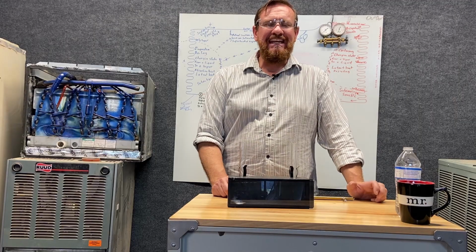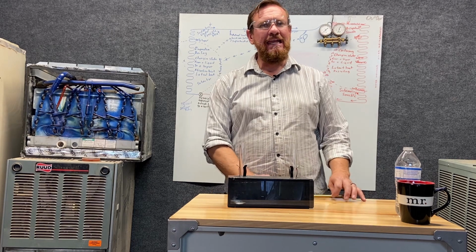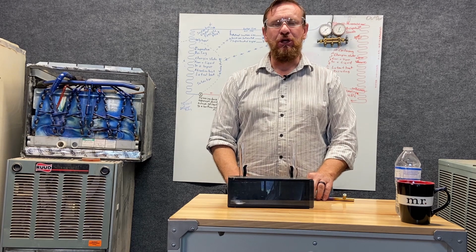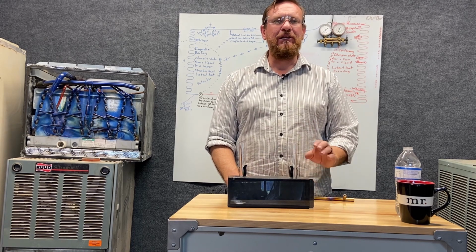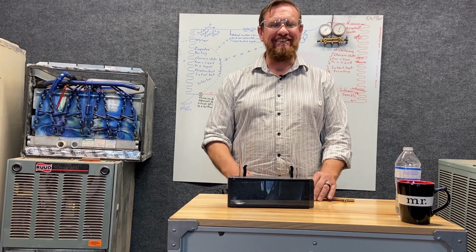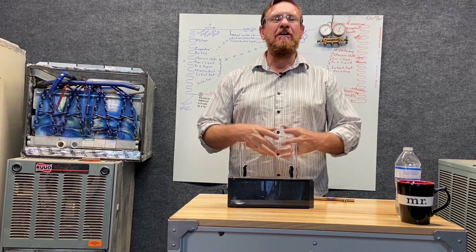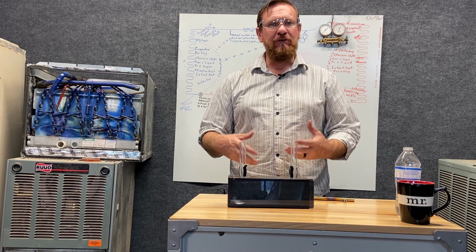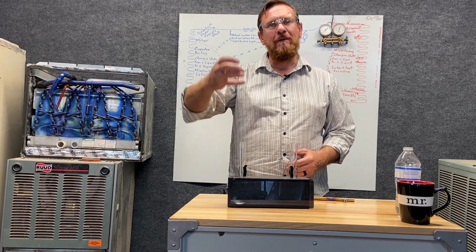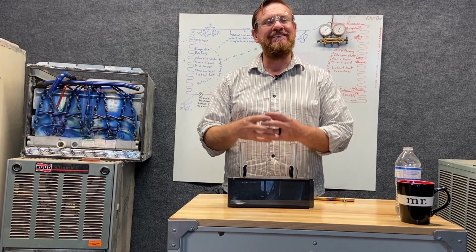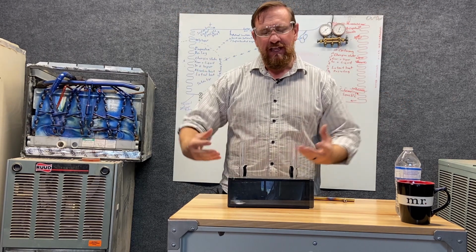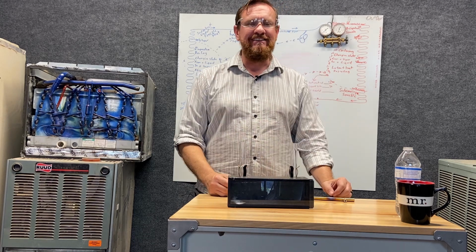So you've heard people say that heat rises. It's really not true. Heat can move in any direction, but because of convection, warm air rises because warm air is less dense. It's a very important thing we need to think of. When we're going to be working with gas furnaces later on, we heat up that fuel, and the fuel mixture is going to travel up and out via natural convection because it's less dense. It's the heavier, denser air pushing down that forces the lighter, less dense air up.